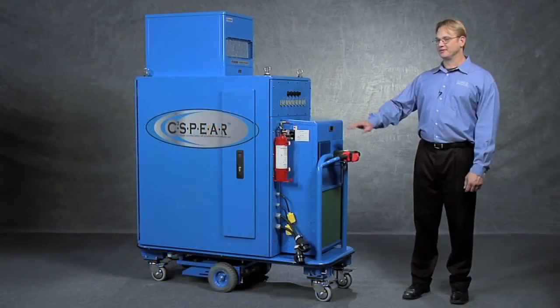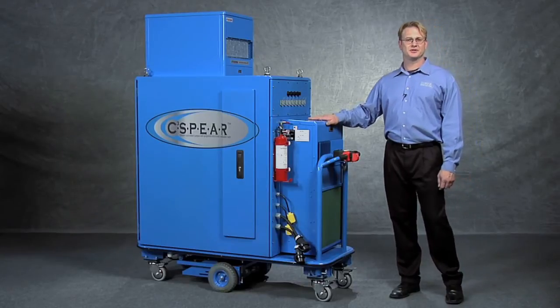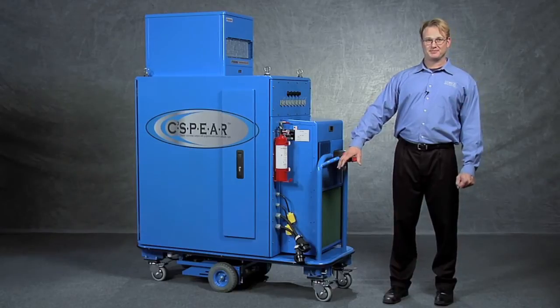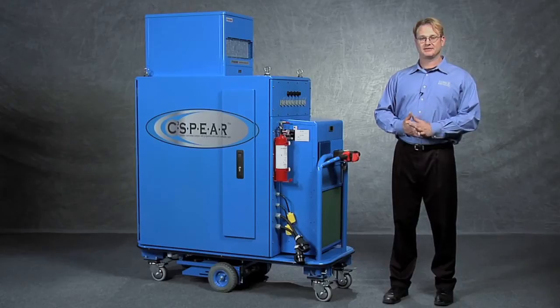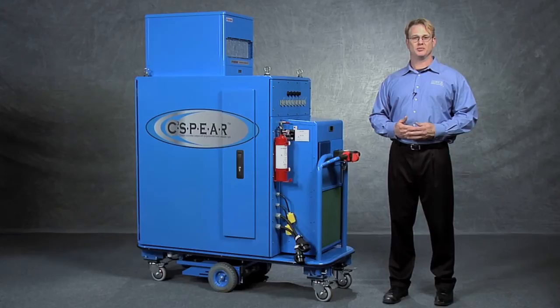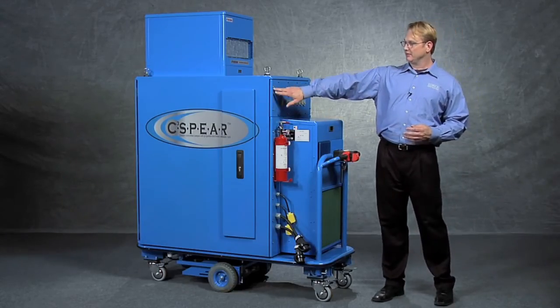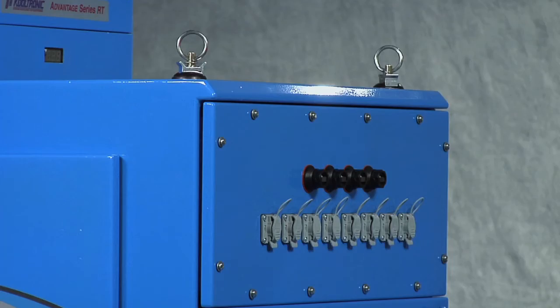Right now I'm standing in front of our NEMA 4 Dual-AC CSPEAR. It shares many features with our standard NEMA 12, including the mobile base and mobile cart. In particular, its key features are that it's NEMA 4, which means it's waterproof and resistant up to power wash-down. These features are included in the multi-point latch or bolting system for the patch panel and all of the IP67 connectors for fiber, USB, and RJ45.